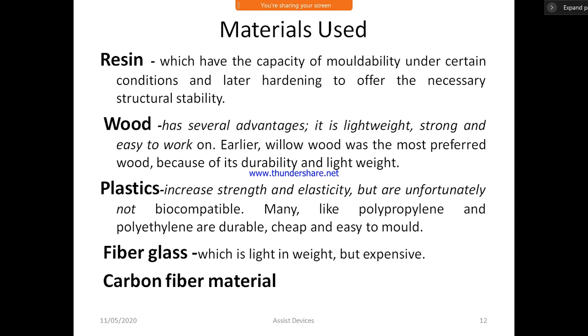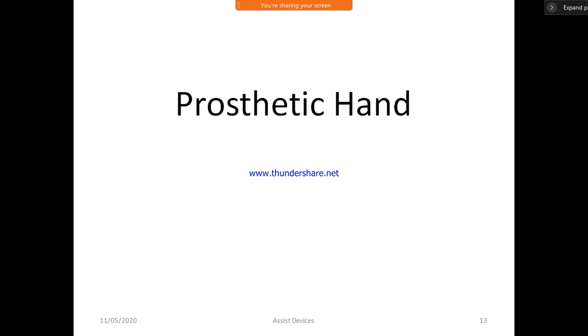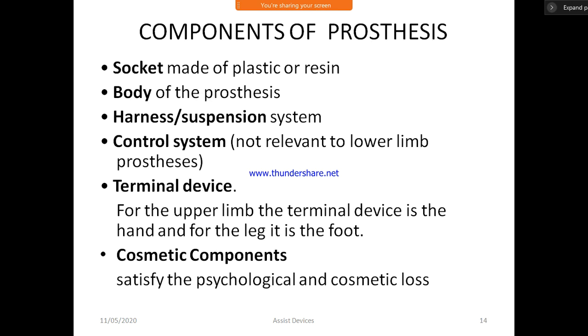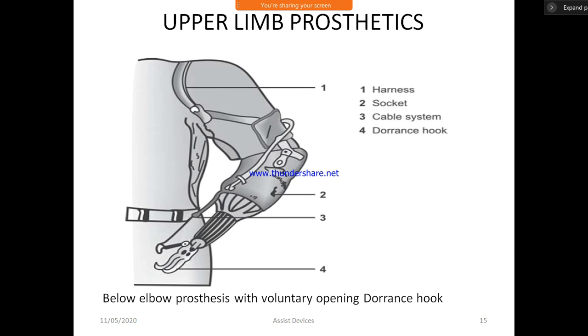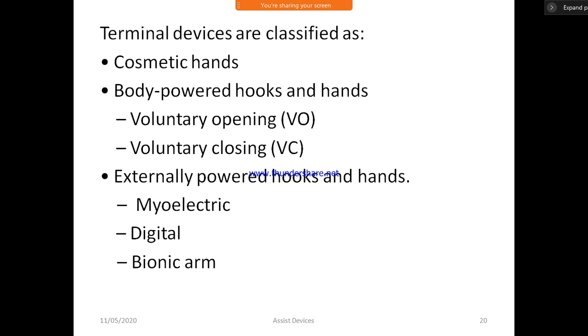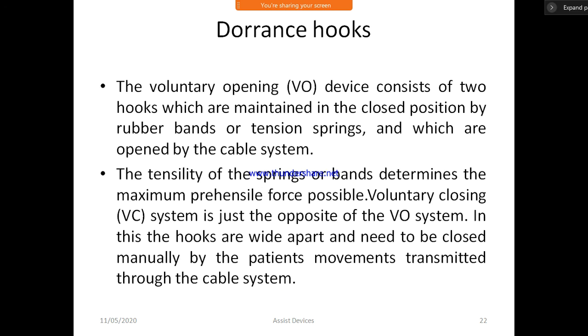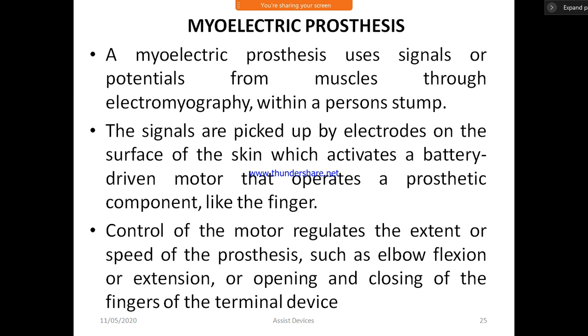The voluntary closing system is just the opposite of the voluntary opening system. Here, the hooks are wide apart and need to be closed manually by the patient's movement transmitted to the cable system. The patient closes the device by pulling the cable on the harness system to grab an object and keeps up the gripping force as long as he wishes to hold it. It can be used to grasp brittle objects with just enough force that it does not break. The disadvantage is that the user has to keep exerting pressure to retain the hold on the object. This is less popular than the voluntary opening devices.